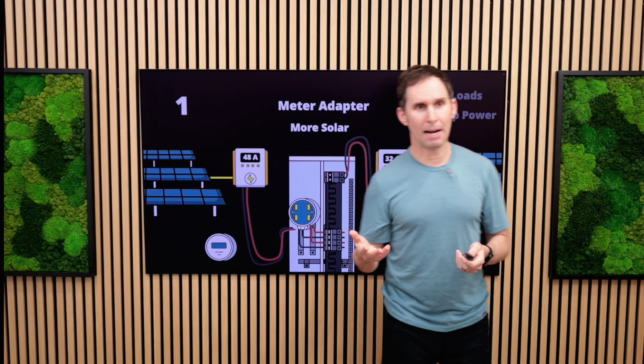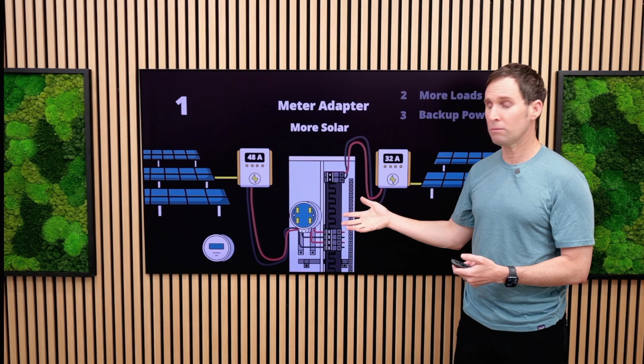When you get a meter adapter that ties in behind the meter itself, you're basically performing what's called a line side tap functionally, and you're able to backfeed more. Why? Because when you're backfeeding from the direction I showed you before, power is coming into the bus bar from both directions. When power comes in from both directions, functionally you have less control of how much energy is being used, because the main breaker alone isn't what's protecting the main bus bar.